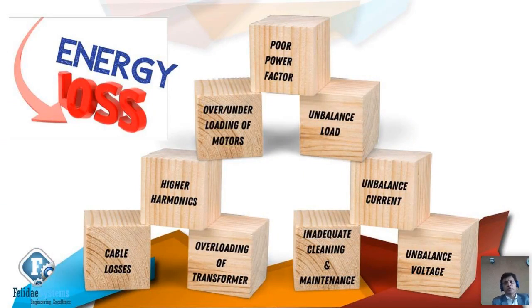Of course, I am pretty sure that we all have seen these losses once or twice, but let me just brief you in a quick way. One is low power factor, poor power factor. Power factor is a very critical parameter, not just for billing purposes. You may have a better power factor at the billing station, I mean, near the transformer. But I would suggest if your facility is bigger, start putting the power factor correction panel at distributed locations, because that will reduce the losses of the cable also, and the load on the cable will go down. The I square R losses of the cable will be reduced, and at the same time the load on the switch gear will be reduced. The facility will be safer, and the correction of the power factor will be much better.